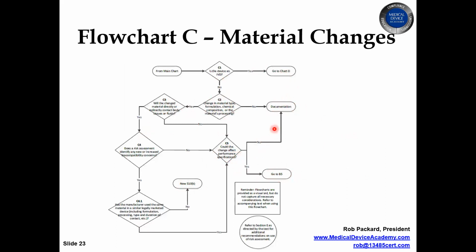The answer is possibly yes, possibly it's documentation. But the routes to that are: no, it's not a change in the formulation; or it doesn't contact tissues and wouldn't affect performance; or it does have contact, but it doesn't increase or affect the biocompatibility and doesn't affect performance. So it's fairly complex to get to a documentation-only outcome. Most of the time you end up with material changes being new 510Ks if it's a patient-contacting material.